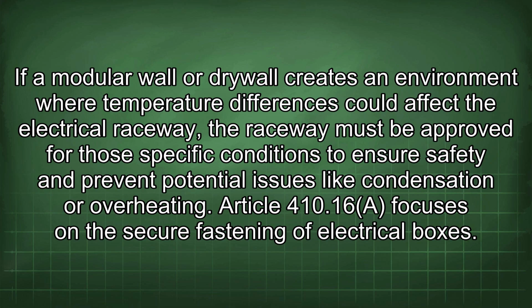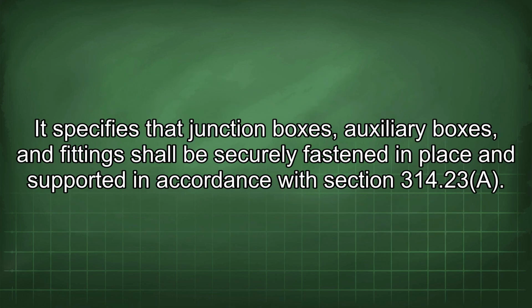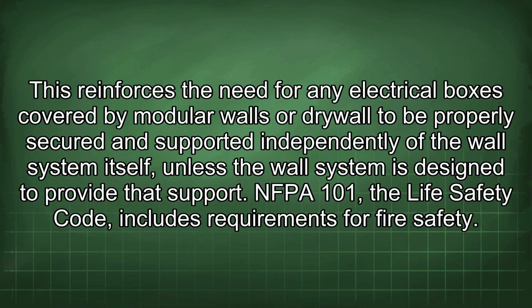Article 410.16 focuses on the secure fastening of electrical boxes. It specifies that junction boxes, auxiliary boxes, and fittings shall be securely fastened in place and supported in accordance with Section 314.23(A). This reinforces the need for any electrical boxes covered by modular walls or drywall to be properly secured and supported independently of the wall system itself, unless the wall system is designed to provide that support.